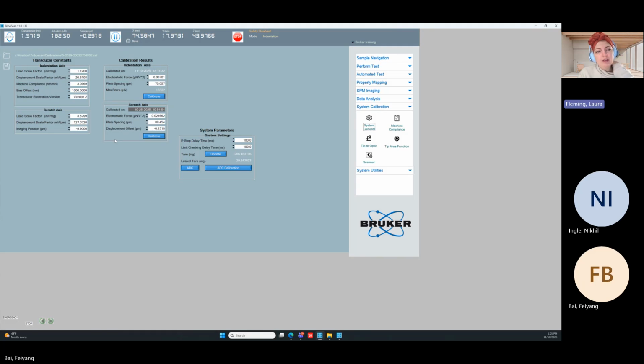Good. So here we have our transducer constants. We've talked quite a bit about the indentation axis calibration constants. Similarly, for the scratch axes, we do have a load scale factor and displacement scale factor. These are the relationships between load and applied voltage and displacement and measured signal. So each transducer has a unique scratch axis calibration as well. And then there's also an imaging position, which we just talked about. That is the offset in the scratch axes.